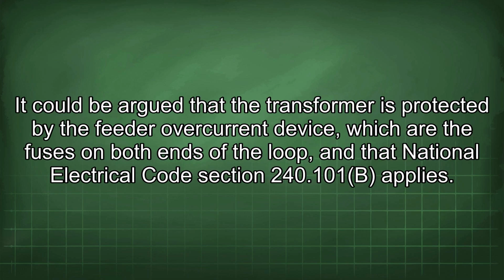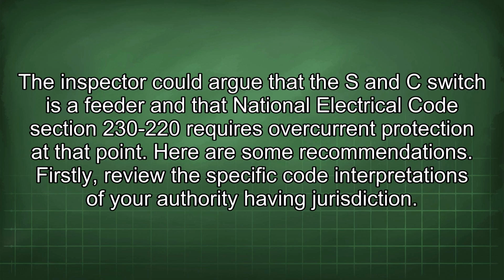It could be argued that the transformer is protected by the feeder overcurrent device, which are the fuses on both ends of the loop, and that National Electrical Code Section 240.101b applies. The inspector could argue that the S and C switch is a feeder and that National Electrical Code Section 230-220 requires overcurrent protection at that point.